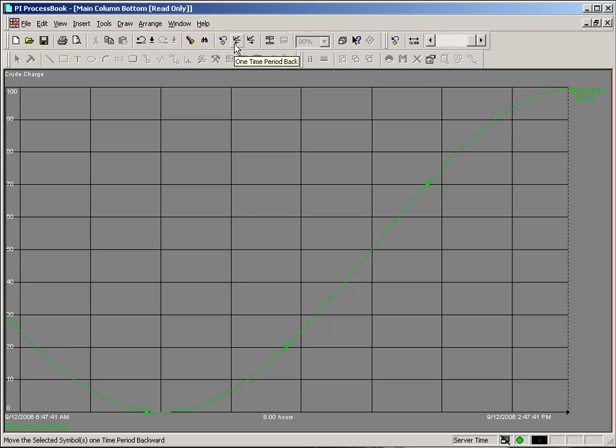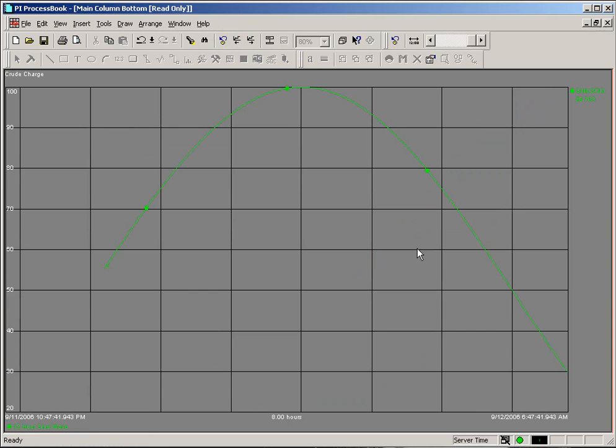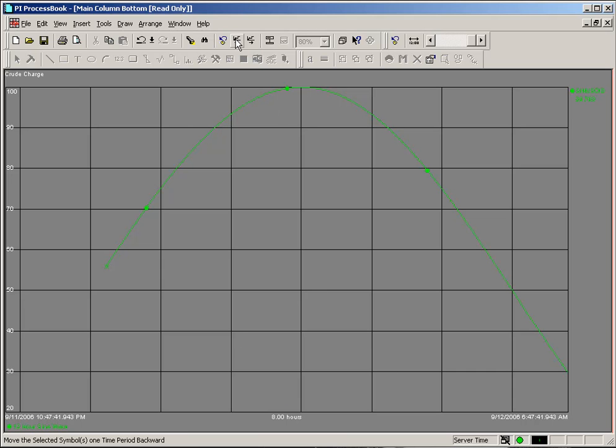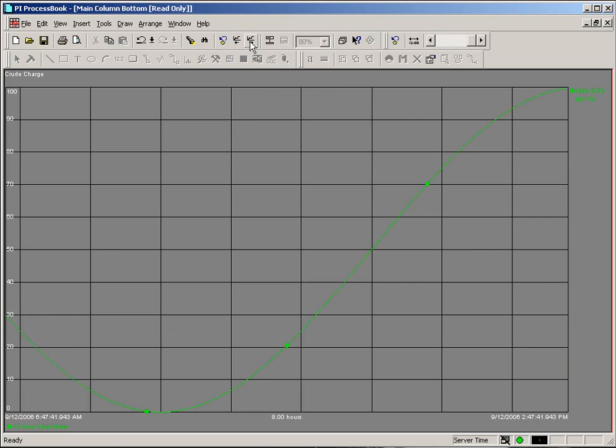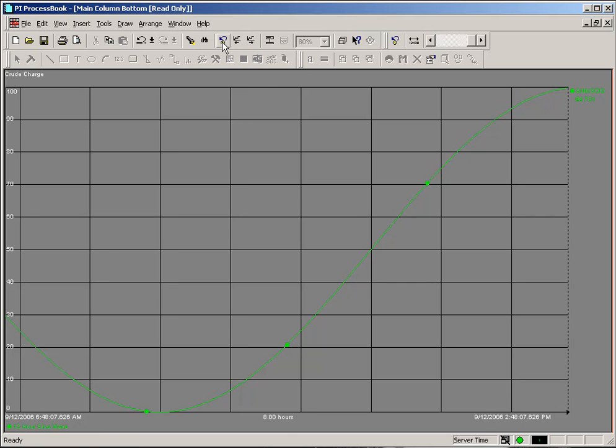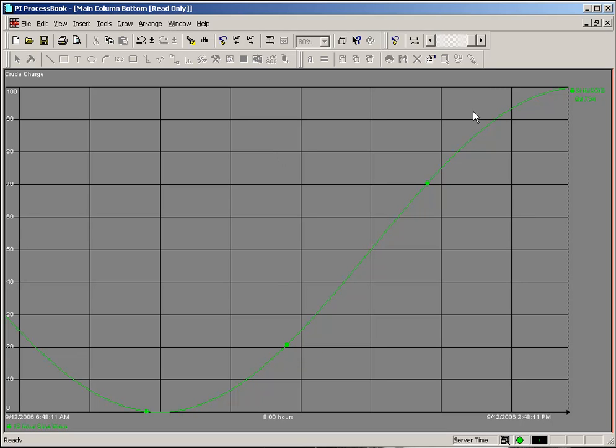The one time period back will look at the time range of the trend and go back one unit. This particular trend happens to be an eight hour trend. So every time we click that one time period back, we go back eight hours. And thus, every time you click on one time period forward, you go forward in time eight hours. Again, the revert time range will return the trend to its original state.